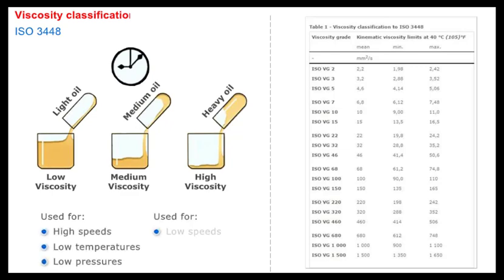From an application point of view, lighter oils, normally up to VG22, are used for pneumatic applications. Higher viscosities, traditionally between VG32 and VG68, for hydraulic systems. ISO VG100 and VG150 are commonly found in circulation systems, while viscosities between VG220 and VG680 are found in gear applications.